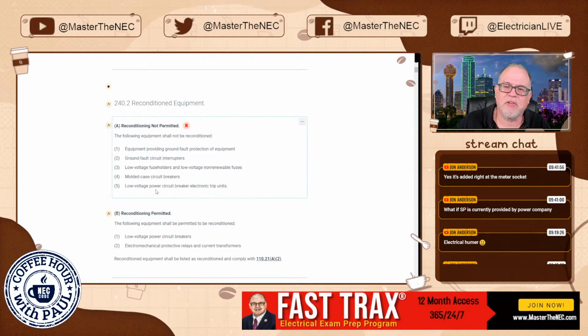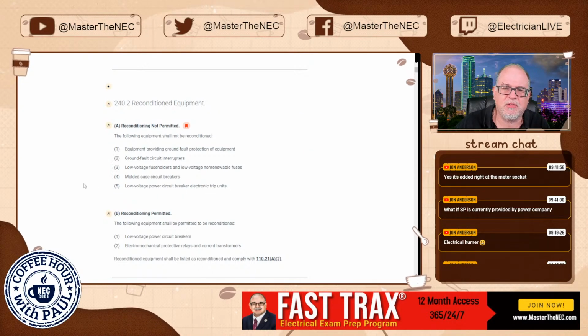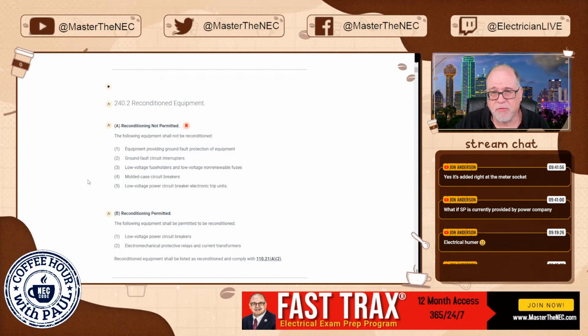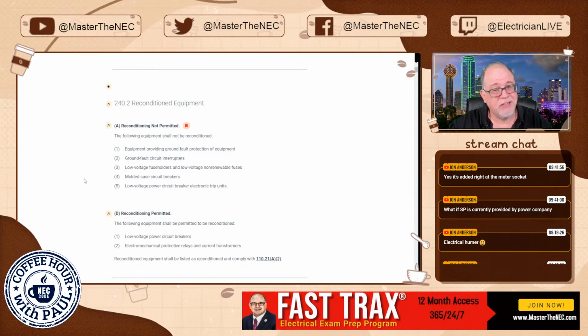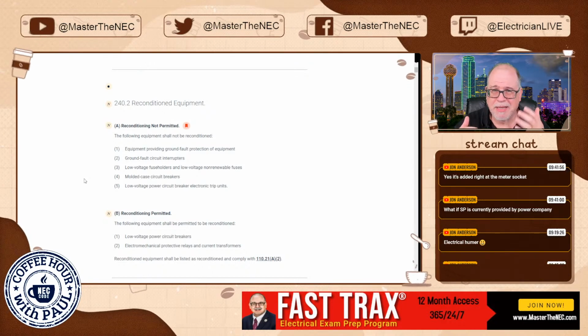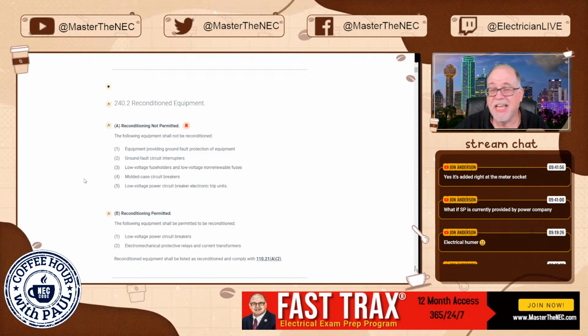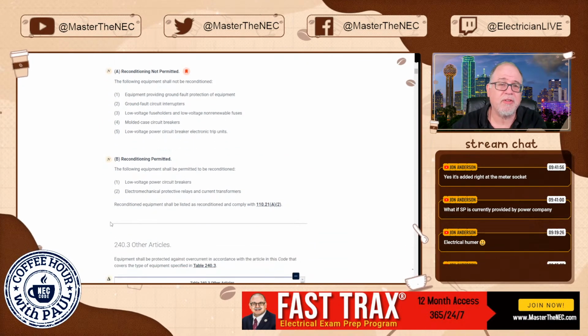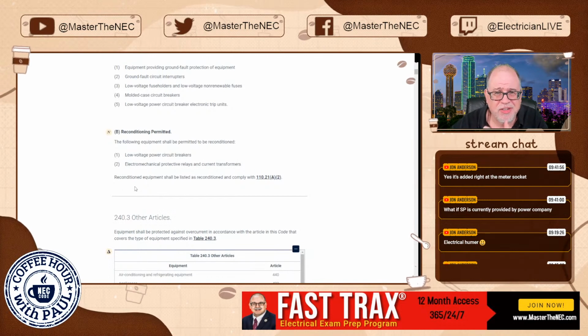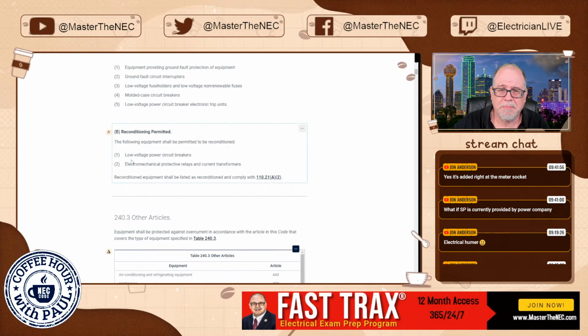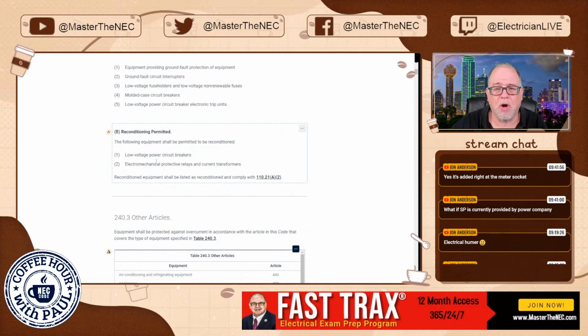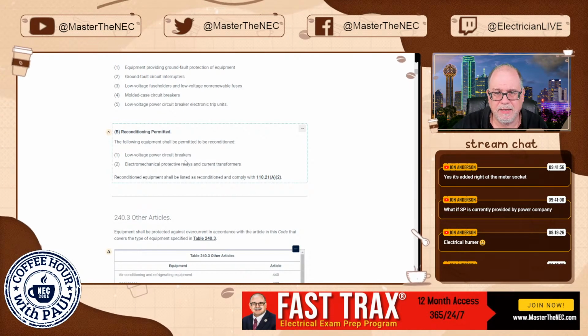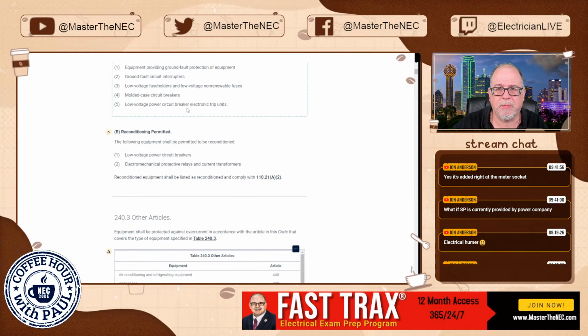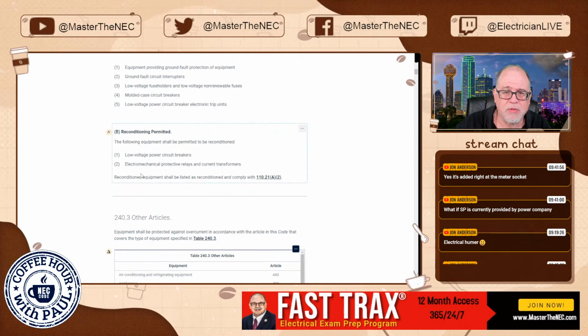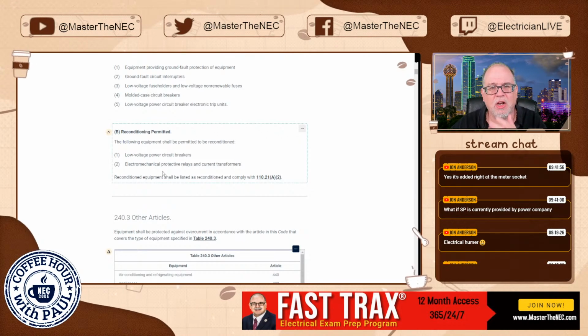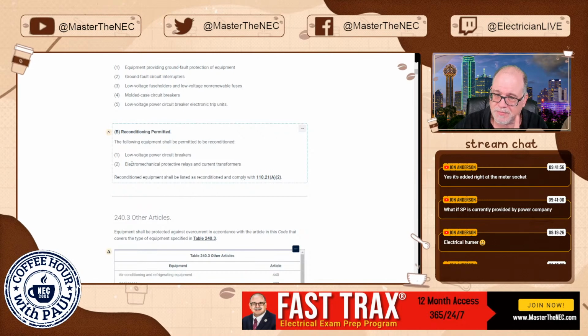And of course, low voltage power circuit breakers with electronic trip units. Okay, low voltage being, you know, 1,000 volts or less, 600 volt applications. Those, again, electronic trip units. Think about the components in these things. No, you're not going to recondition it. However, there are some things that are reconditionable, and these didn't change from the previous edition, but we want to talk about it. So low voltage power circuit breakers, okay? These aren't low voltage power circuit breakers with electronic trip. They're just low voltage power circuit breakers, and they'll be marked as such, low voltage. Not the same as a molded case circuit breaker, okay?